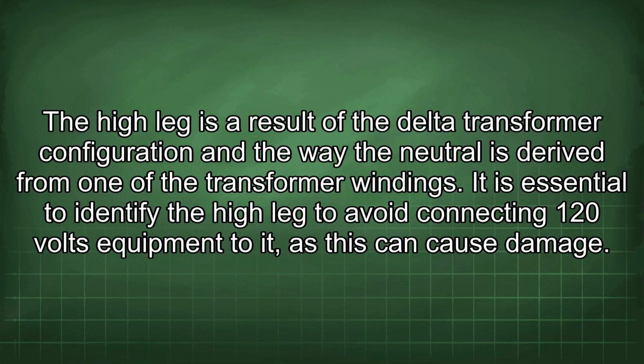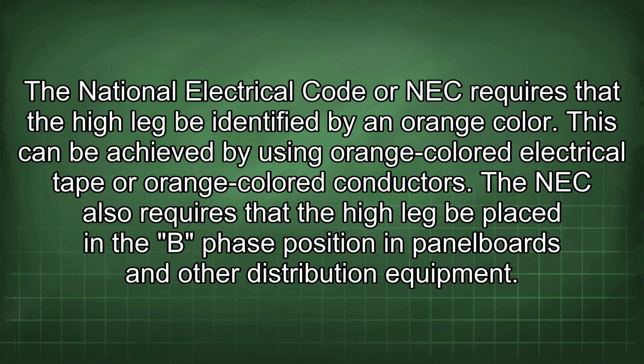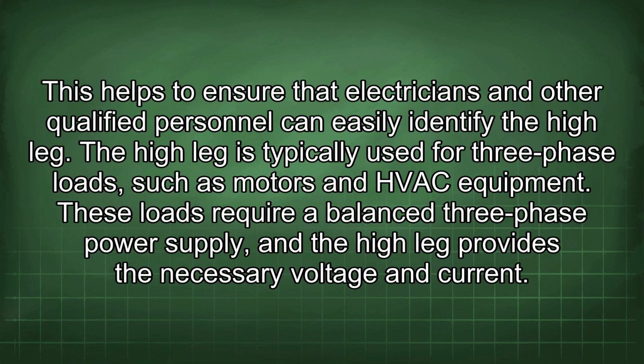It is essential to identify the high leg to avoid connecting 120 volts equipment to it, as this can cause damage. The National Electrical Code, or NEC, requires that the high leg be identified by an orange color. This can be achieved by using orange-colored electrical tape or orange-colored conductors. The NEC also requires that the high leg be placed in the B phase position in panel boards and other distribution equipment. This helps to ensure that electricians and other qualified personnel can easily identify the high leg.